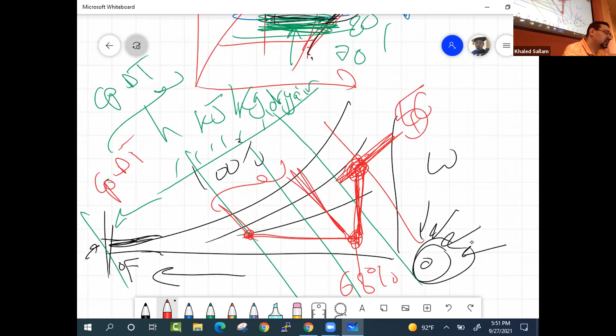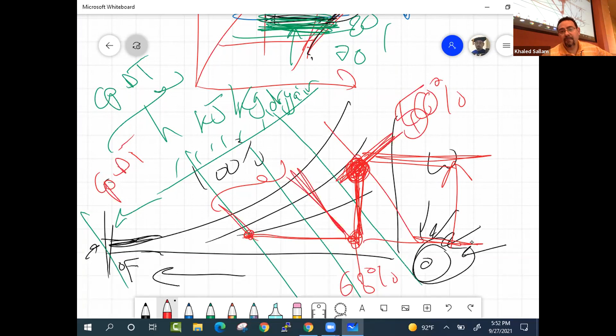We started with 0, and this comes from the desired condition. What is the desired condition? You want to be here, at 68 degrees and whatever humidity - was it 40% or 60? What was it... 50? So whatever that point is, you want your W to go up to this, going from here to here. So at 68 and 50%, you get that number, assume the start is 0, right?